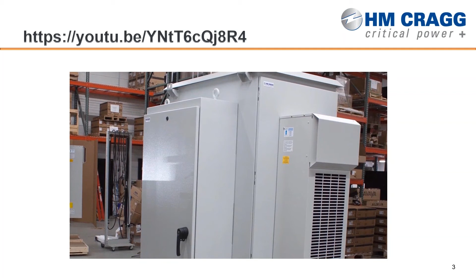Some of the challenges we saw in this were the UPS being a large unit and fitting it inside of an outdoor enclosure, utilizing the wall mount bypass within the system, and keeping everything in a watertight containment. Also the cooling provisions we needed to provide, as this was going into a hot, humid environment out on a tarmac. So we partnered with CPI for the armor enclosure designs, as well as Pfannenberg on the cooling.